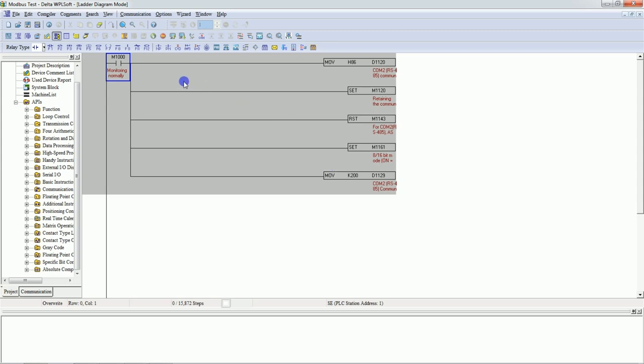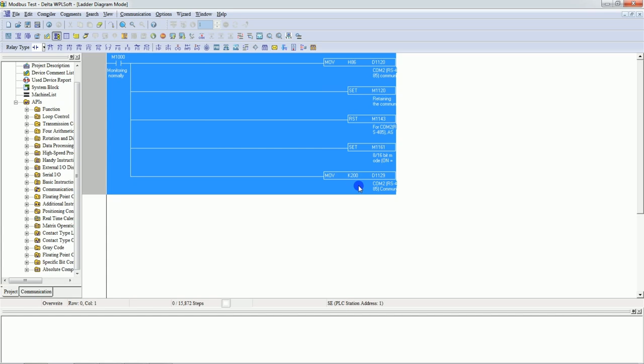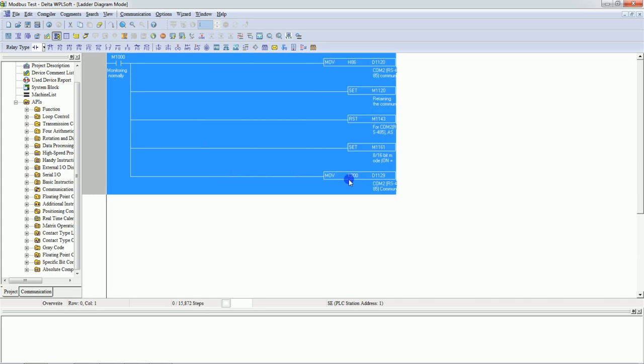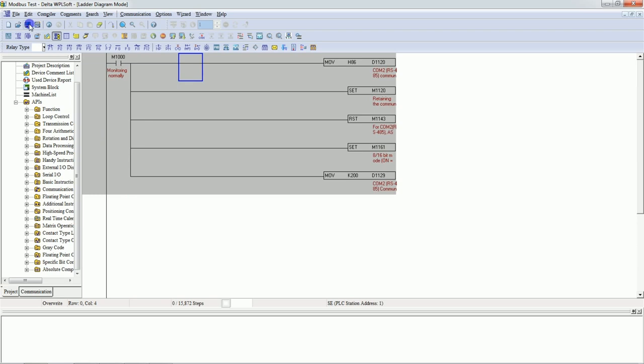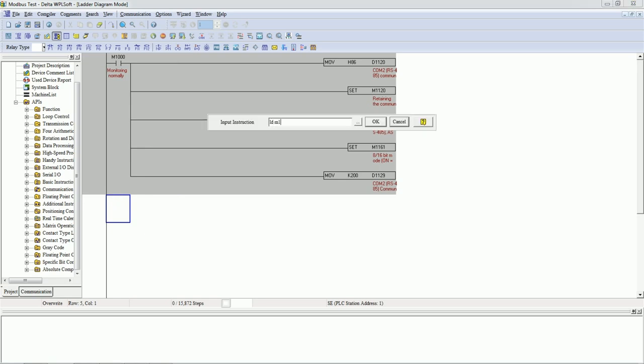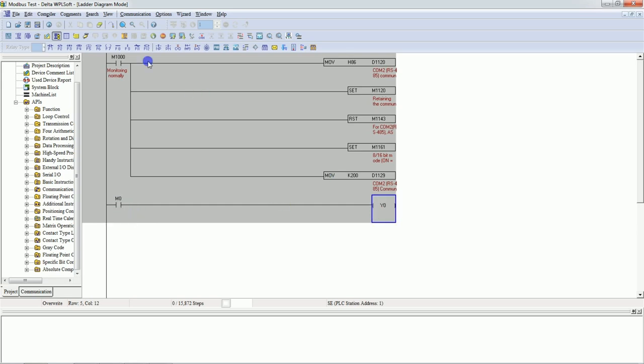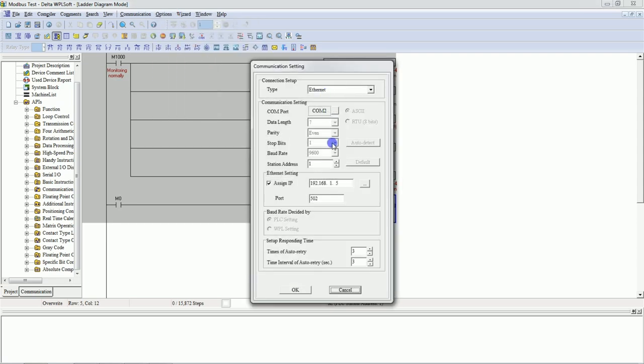This is the Modbus program. We need to first configure all Modbus parameters — in this program we have configured all parameters of Modbus. We will just save this. Now we will write some code: LD M0, OUT Y0 — means if M0 is ON then Y0 will be ON. We will download the program. The PLC is connected through Ethernet, so I will check Ethernet and click OK.